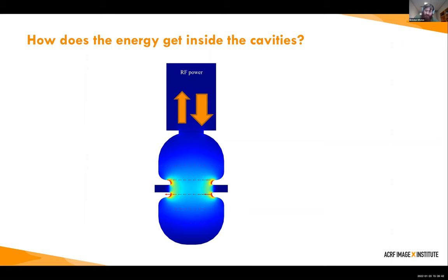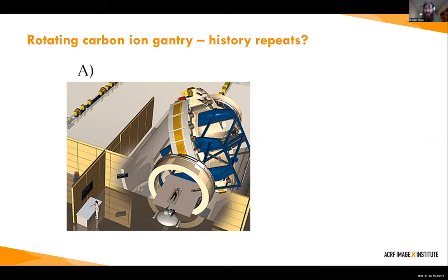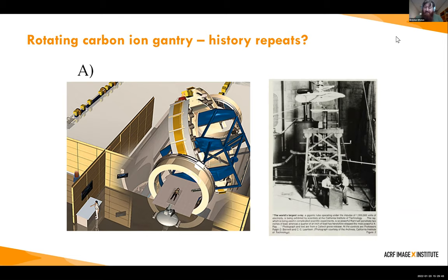This is a rotating carbon ion gantry — an exception to my rule of not talking about other particles. Carbon ions are a very advanced form of radiotherapy with very favorable characteristics, but they're very difficult to produce and control. That structure is absolutely giant, which is obviously problematic in terms of cost, size, and ability to treat many people. I like to show this in the context of our earlier picture from about 60 years ago, because we were in a similar spot with electron acceleration — multi-story structures just to produce a fairly low-energy beam.